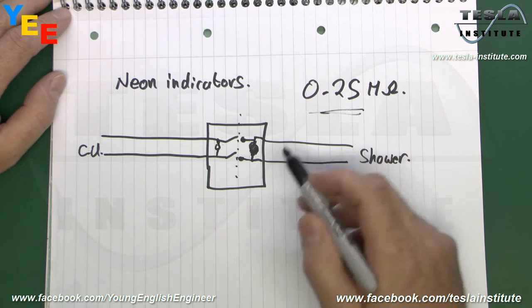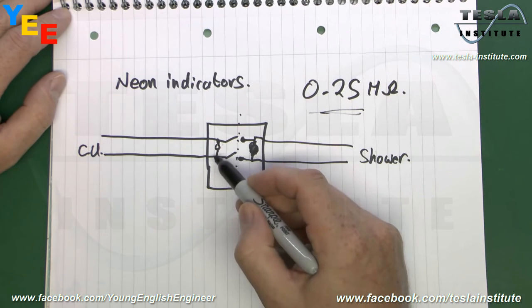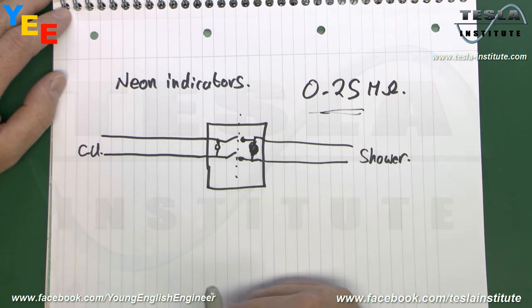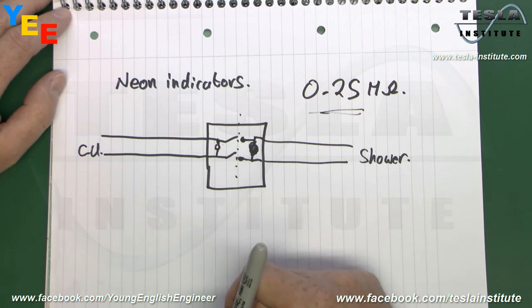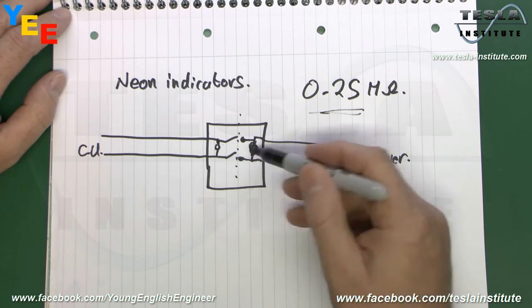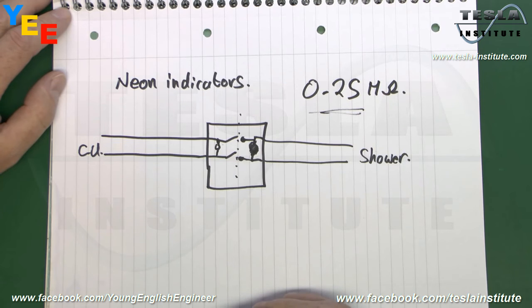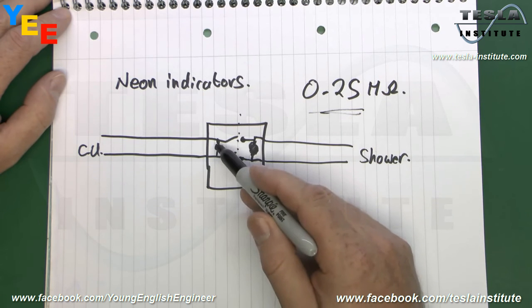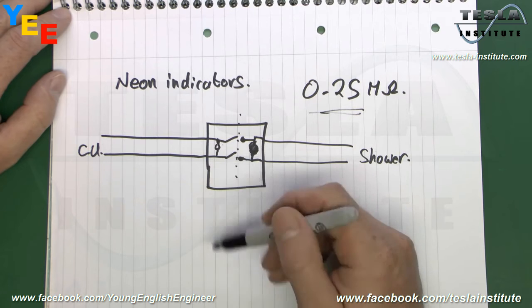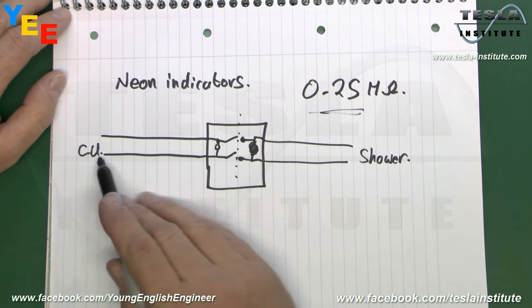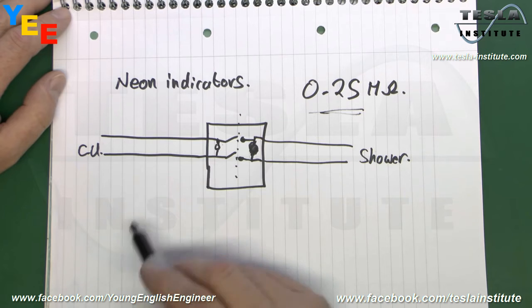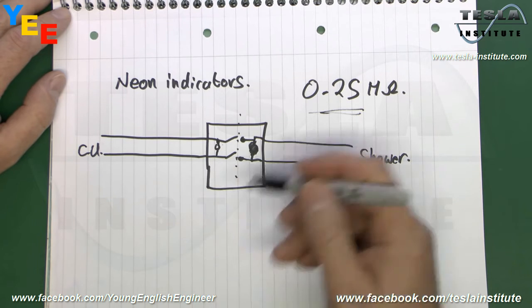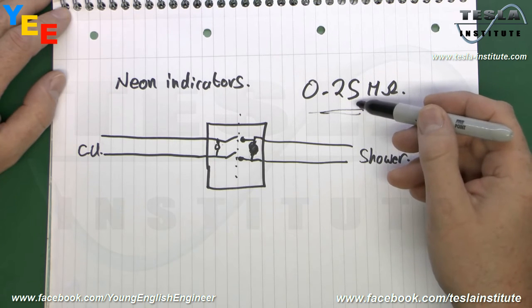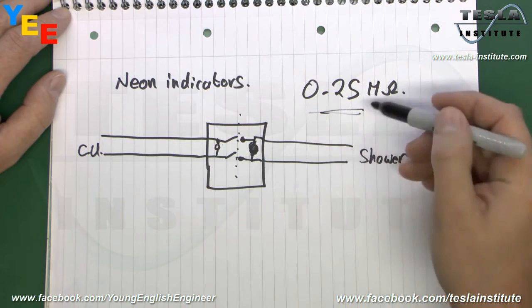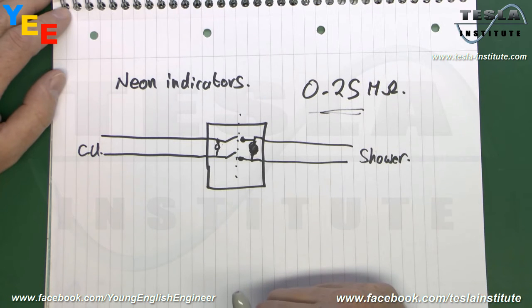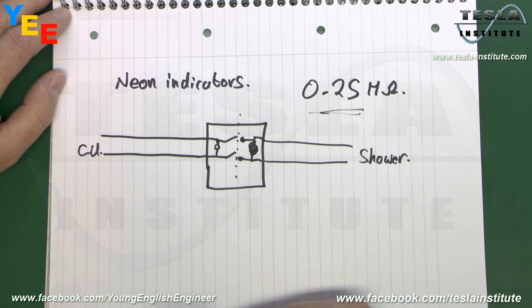So if you get something like that, it's probably due to a neon indicator in a switch, or say an isolator, which may or may not be in the correct wiring arrangement, or it may have simply been left on by mistake. Interestingly, neons only work or conduct above about 70 volts. So if you put a continuity test here, let's say only a few volts, it'll show as a completely open circuit. It's only when you put the voltage up to the sort of hundreds that you'll actually get it to light up, and then you'll see that fairly low reading in terms of the insulation resistance.